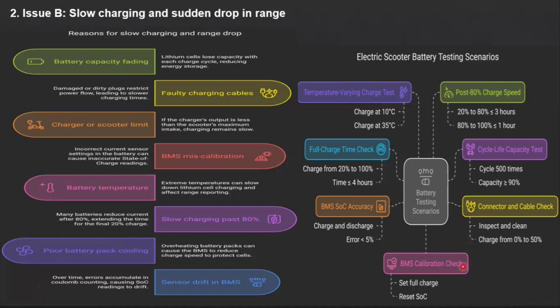BMS calibration check: set full charge and reset SOC. BMS SOC accuracy: charge and discharge error less than 5%. Full charge time check: charge from 20% to 100%, time less than or equal to 4 hours. And the temperature varying test that we already discussed.